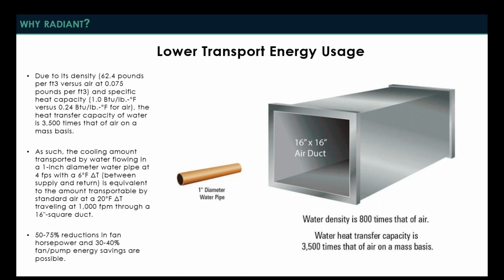Another primary reason that radiant is great, and this is one of my favorite images, and I always talk about this when I'm having any discussion with an architect or an engineer who's interested in the technology, is that the lower transport energy usage has a huge benefit for radiant systems. You can see in the image here, we have a 1-inch diameter pipe and a 16 by 16 air duct. Well, due to the density and heat transfer capacity of water versus air, those two objects can transfer the same amount of energy. So when you're talking about very small pipes and pumping fluid versus very big ducts and pushing air around, you can find 50 to 75% reductions in fan horsepower when you're using a radiant system over an all-air VAV type system. And all in, when you're looking at both fan and pump energy, savings on the order of magnitude of 30 to 40% are possible.